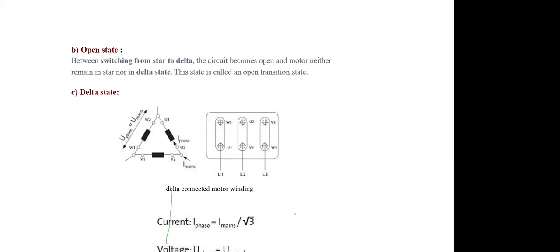This is what I said, that between switching from star to delta, the circuit becomes open and the motor remains neither in star nor in delta state. This state is called an open transition state. So my suggestion is that you generally try to avoid this open state before the motor reaches synchronous speed.